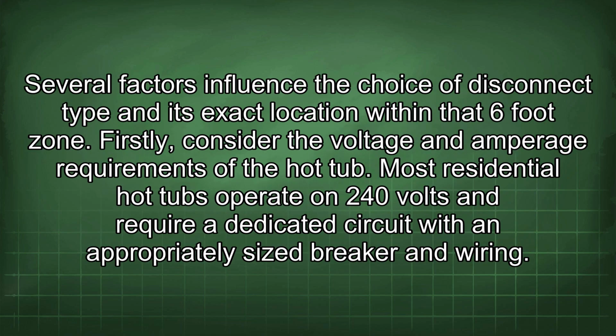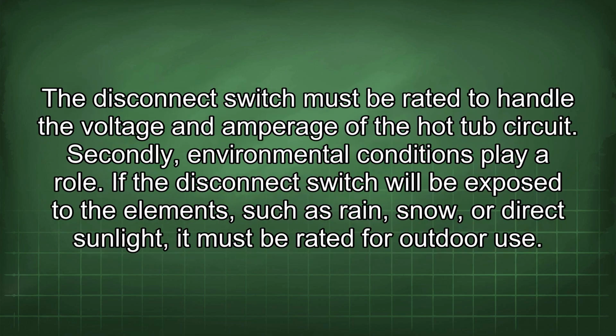Several factors influence the choice of disconnect type and its exact location within that 6-foot zone. Firstly, consider the voltage and amperage requirements of the hot tub. Most residential hot tubs operate on 240 volts and require a dedicated circuit with an appropriately sized breaker and wiring. The disconnect switch must be rated to handle the voltage and amperage of the hot tub circuit.